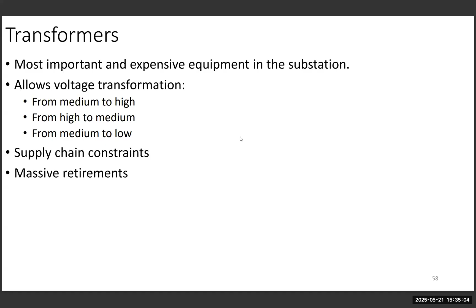The bushing, the fans - like I said before, there was a question about using multiple resources, more than one, DGA and so forth. Right now there's a big issue with the supply chain because it could take double or triple - you may have to wait 4 years for a transformer. So you don't want to be that one engineer who missed the alarm and lost a $10 million transformer and then have to wait 4 years, having fun explaining to upper management that the transformer is going to arrive by 2029 for something as simple as missing an alarm.